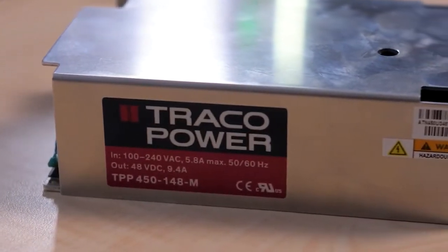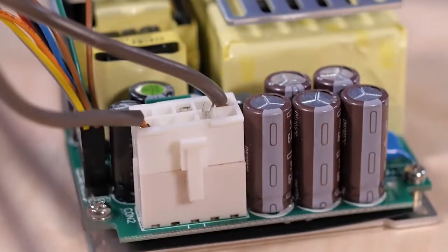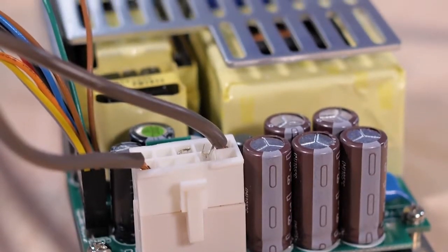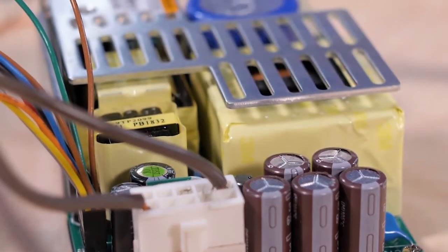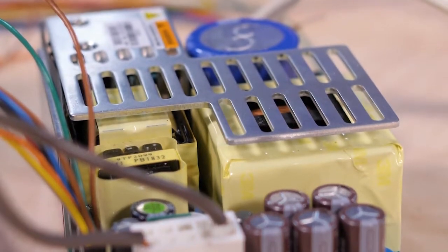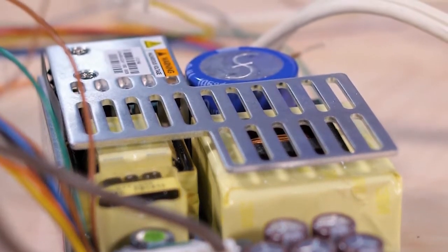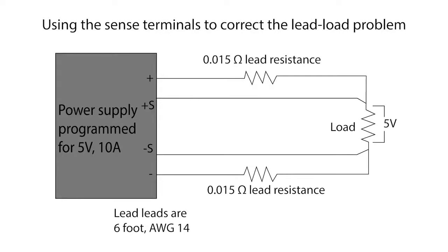The standby pins supply a 5 volt signal and can deliver up to 2 amps to external circuits, as might be used during a wake-up event at the system level. And it can be used to power up the remote control feature as well. Finally, there are 2 sense pins in the auxiliary connector used to compensate for power losses in long load cables, so you can get output voltage regulation at the load rather than at the converter's output terminal. The remote sense feature can compensate output voltage drops of up to a half volt.